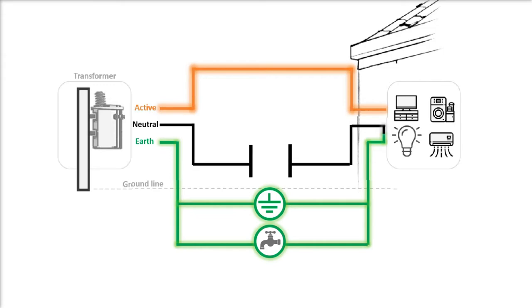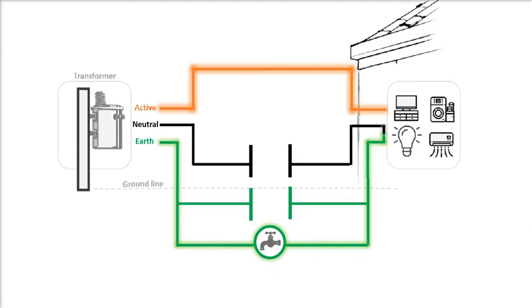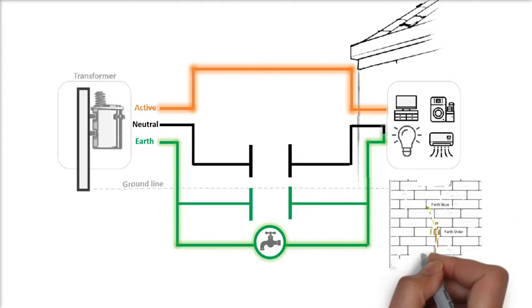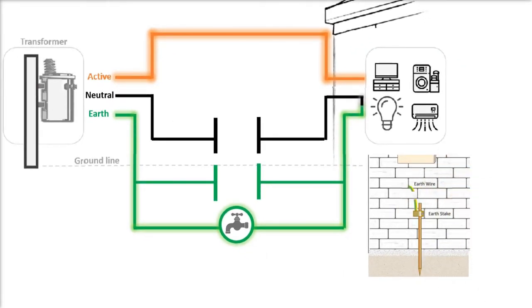Okay, but what if the earth connection also gets broken? Then most of the electricity will use the water pipes connection as its return path. And a break in the earth connection means that the safety switch or circuit breakers cannot be activated. This can be a problem because electricity always looks for the easiest way back to the source, the transformer, through the path of least resistance.